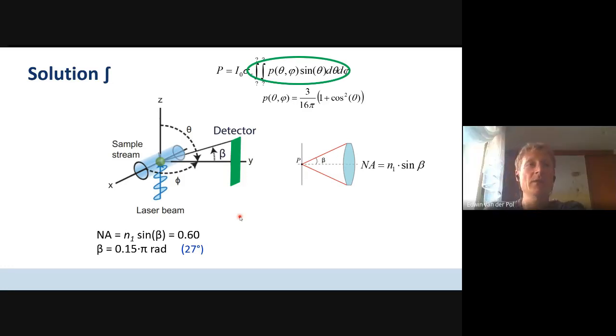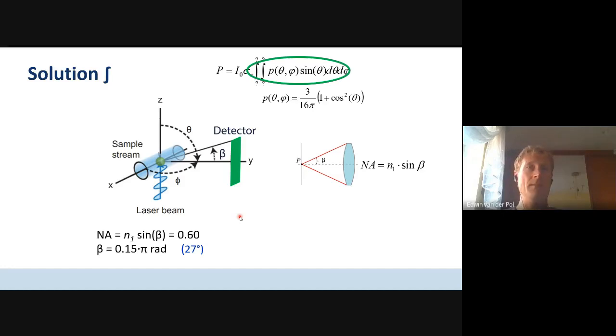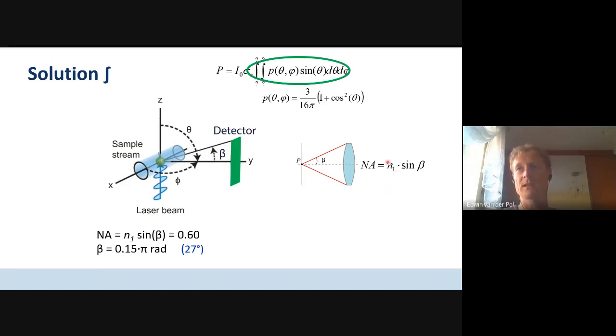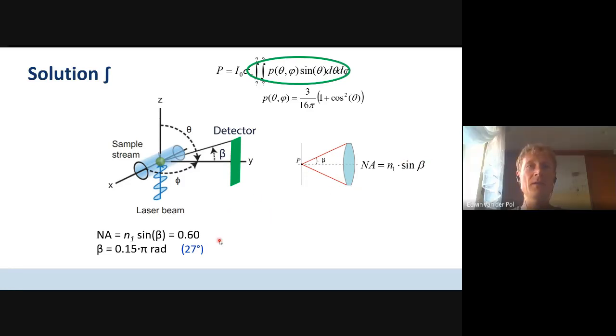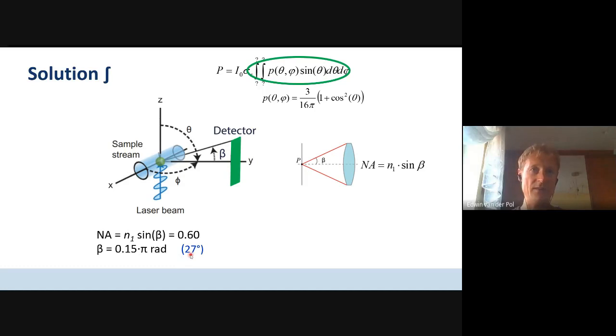Then, choosing the boundaries of the integral — as we discussed — one thing which needs to be calculated first is the maximum collection angle of the lens. That can be done with the formula for the numerical aperture: NA equals the refractive index of the medium times the sine of beta, the maximum collection angle. This lens has a numerical aperture of 0.60, which is quite possible for a flow cytometer, although usually it's higher. Solving the equation, I got beta = 0.15π radians, or rounded, 27 degrees.